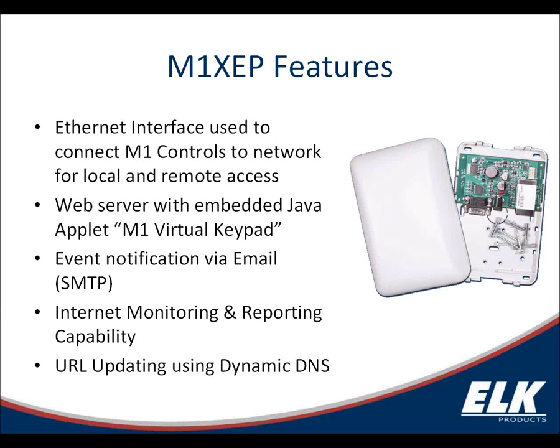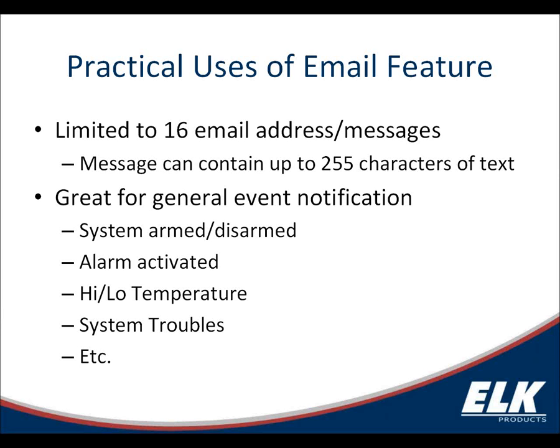We do have the capability of having the system monitored over the internet to a Sur-Gard 3 receiver or to the Osborne Hoffman 2000E software running at your central monitoring. The XEP module does support updating using dynamic DNS. Now, some additional features of the email function of the XEP module is you can have up to 16 email messages. Each message can have up to 255 characters of text.